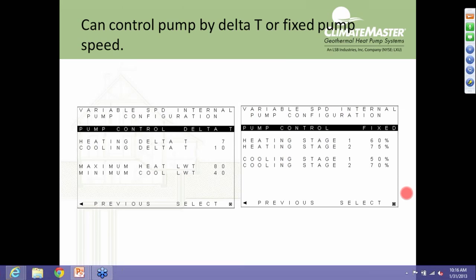You can also control the variable speed pump at a fixed pump speed. But I would caution you in doing this, you really need to fully understand, because now no longer will the pump be ramping up and down. It's going to go to a fixed speed in a particular mode of operation, heating stage 1 and 2, cooling stage 1 and 2. And you really have to understand your loop field, that you've got the right flow rate at that particular pump speed, that it's going to perform the way it needs to perform, as well as your heat pump. So I really caution you in using fixed speed pumping unless you really got your arms around what's going on in your whole system.